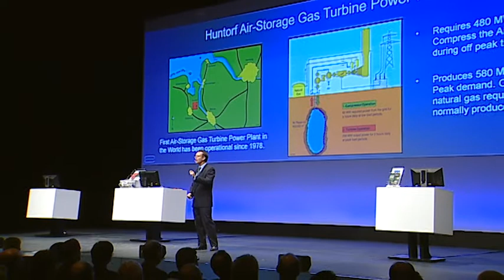The efficiency gained by using compressed air allows you to get the same energy from less than a third of the gas you'd typically use. In this particular case, it requires 480 megawatt hours at night to compress the air, and then during the day, when you need it, you can generate 580 megawatt hours. Again, this type of system can be turned on almost instantly.